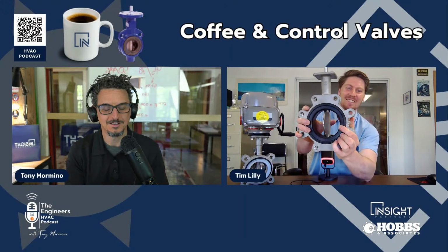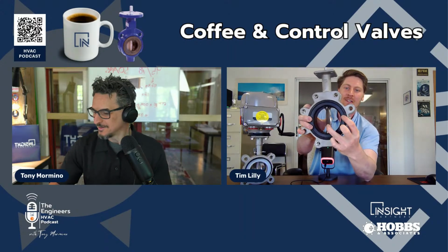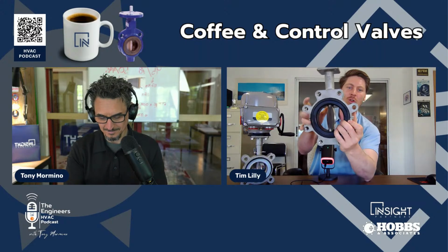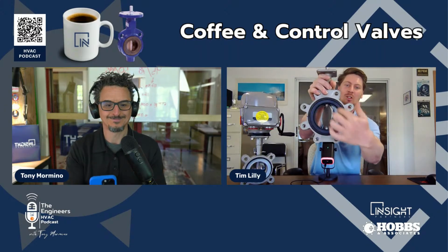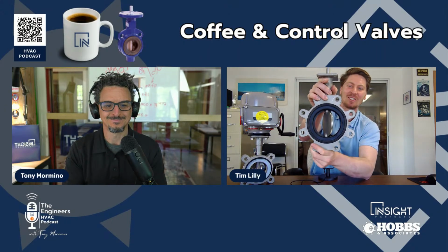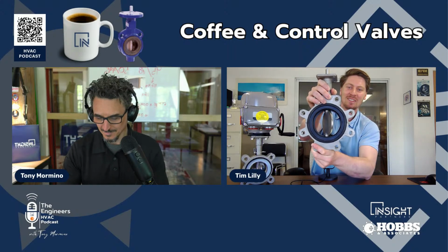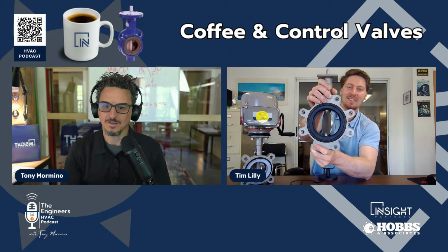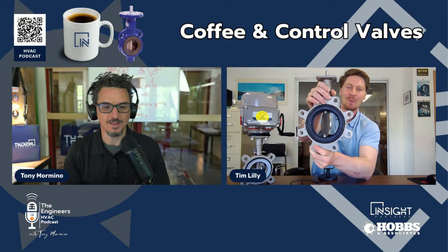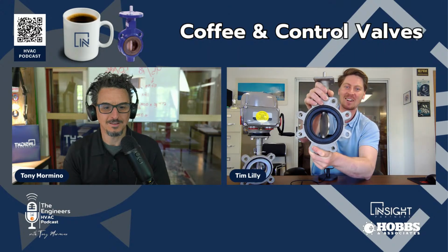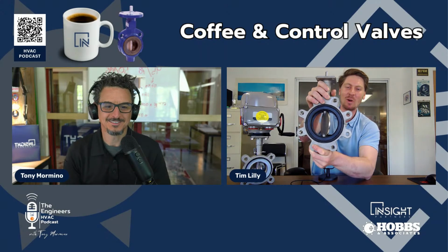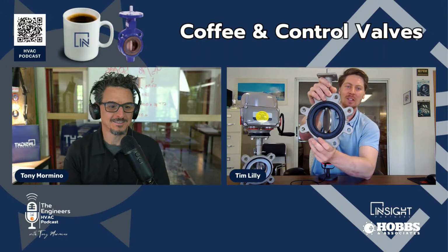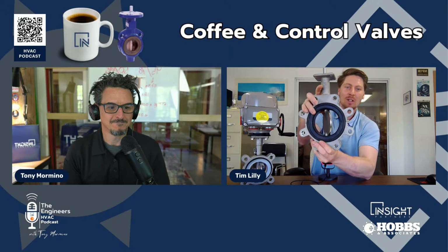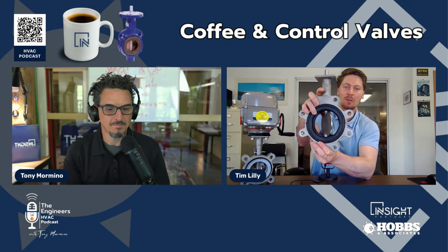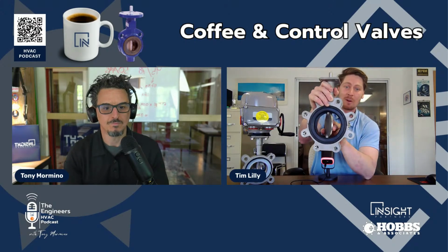So this is your simple butterfly valve with your disc, and what you're trying to do is control the area of your seat, which is a circle. So do you know what the area of a circle is? Let's see, pi r squared comes to mind. That's exactly correct. And so when you're trying to control water through the area of this circle, every time your disc moves, you get an exponential change in your flow. So let's say I'm at 65% open and I jump to 70% open.